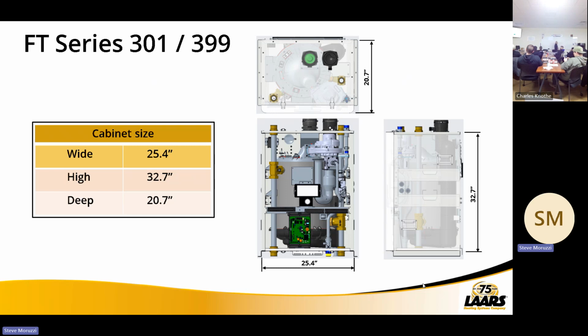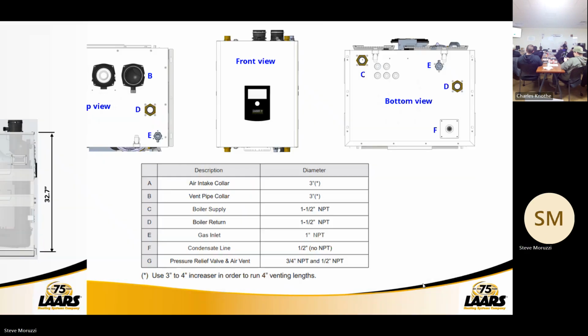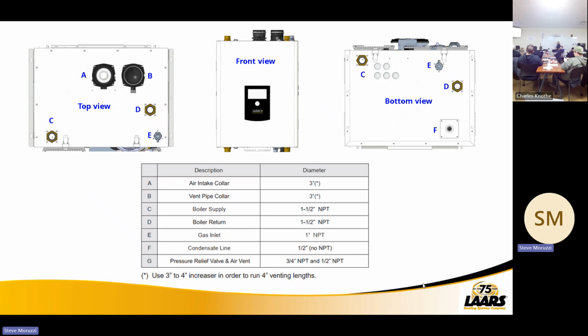Here are your cabinet sizes. So they're small. We're showing top view for your water connections, flue connections and gas connections, and front view and bottom view for your water connections. We can mix and match these boilers. A lot of times when you cascade, depending on the manufacturer, they want like sizes. We can mix and match. We have 2 offerings here, a 301 and a 399. So for example, I can put in 2 301s, 2 399s, and my water connections will all be the same, off the top or bottom.